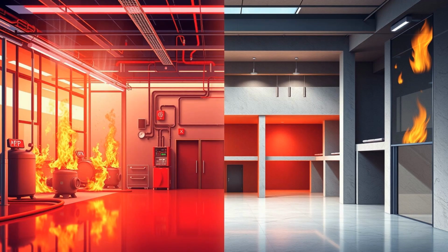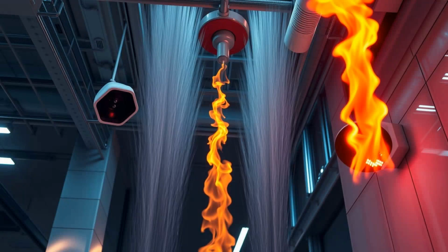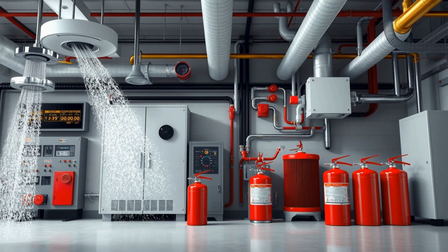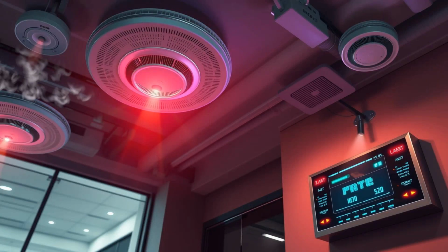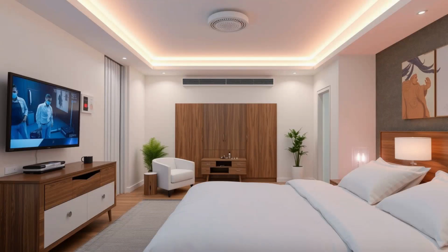Fire protection systems are typically divided into two broad categories: active fire protection (AFP) and passive fire protection (PFP). Active systems are dynamic and reactive. They respond to a fire by detecting it and triggering suppression or alerting mechanisms. These include fire alarm systems, sprinkler systems, gas suppression systems, and portable fire extinguishers. Fire alarm systems are often the first line of defense. They use smoke, heat, or flame detectors to identify a potential fire and send a signal to a central control panel. This, in turn, activates audible and visual alarms to alert occupants.